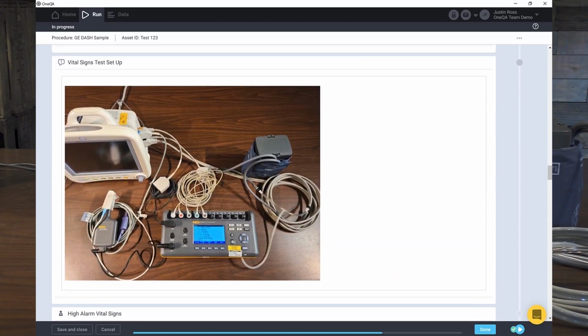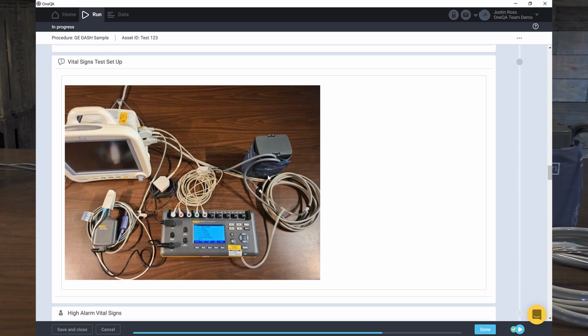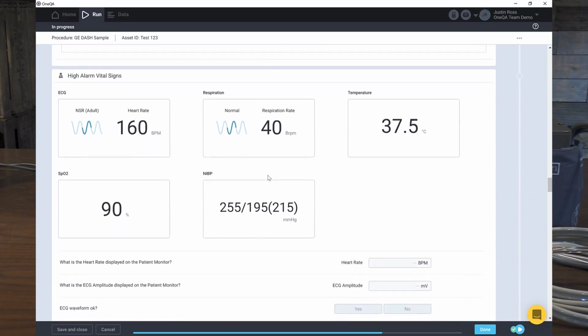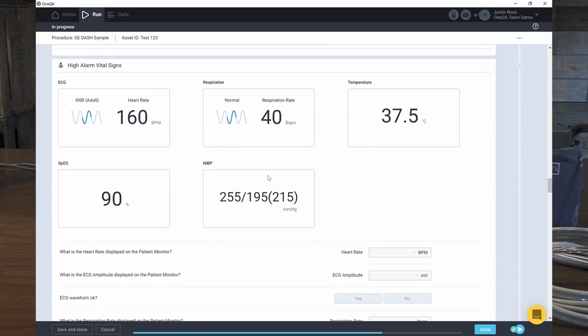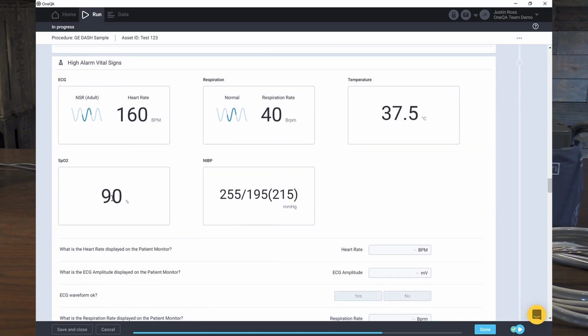Here's my SpO2 to the finger probe. Here's that temperature cable I just showed you connected into the adapter, into the monitor. My ECG, my non-invasive blood pressure that we left in from the prior step. So that's good to go. Now watch this. I go down to the next step here and we're going to test all the high alarm limits with the exception of SpO2 because we can't have too high SpO2. So I just have it tripped for a low alarm.